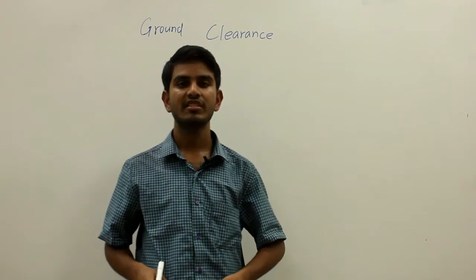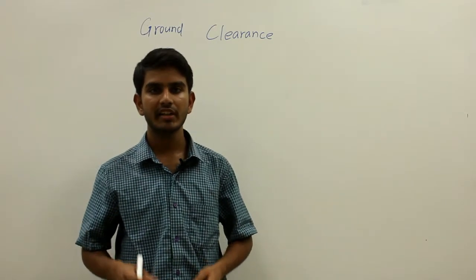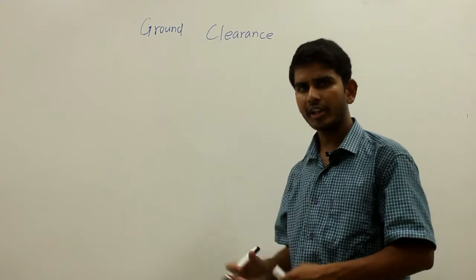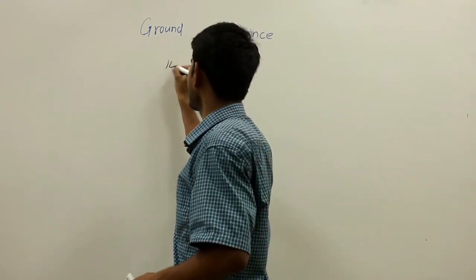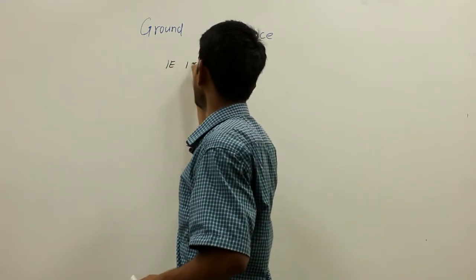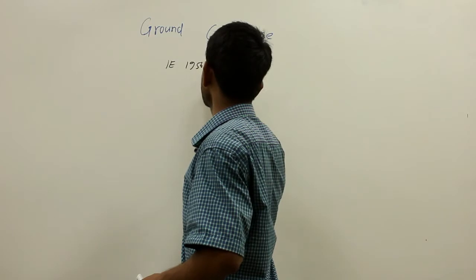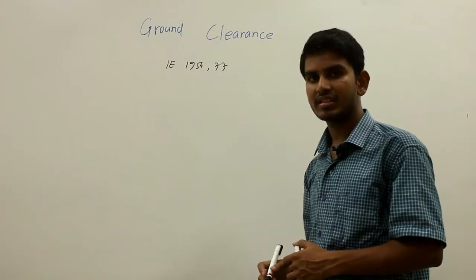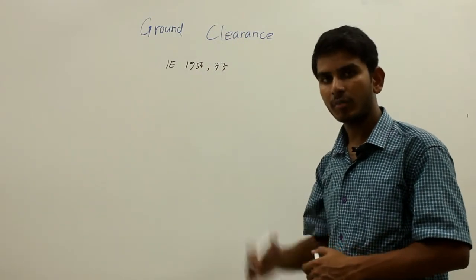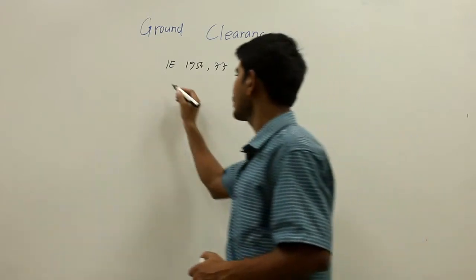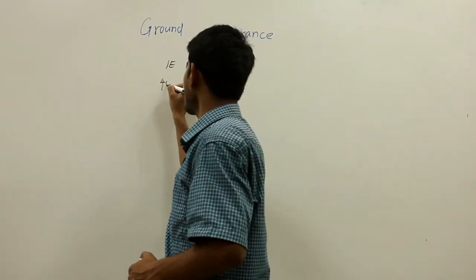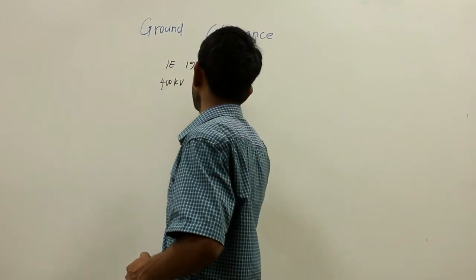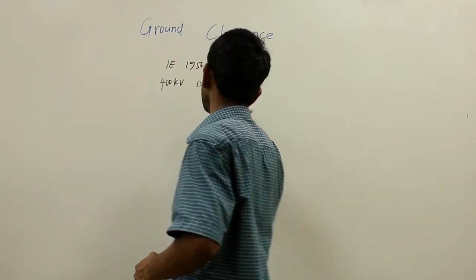Hello friends, in this video let us discuss about the ground clearance of different overhead transmission lines. According to Indian Electricity Rules 1956, Clause 77, the minimum distance between the bottom conductor and the ground of a 400 kV transmission line is 8.84 meters.